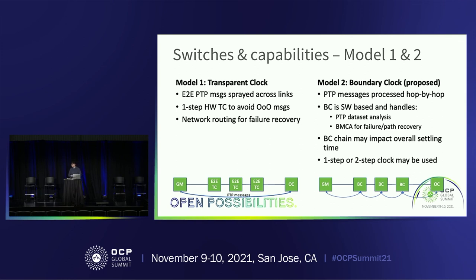In the next phase of the development of the data center profile, we're looking at model two, which is currently a suggestion using a boundary clock. In this case, every single switch device runs a boundary clock. That boundary clock will be processing messages hop by hop, since it will be disciplining its own PHC, and it will become the source for the device that is downstream.